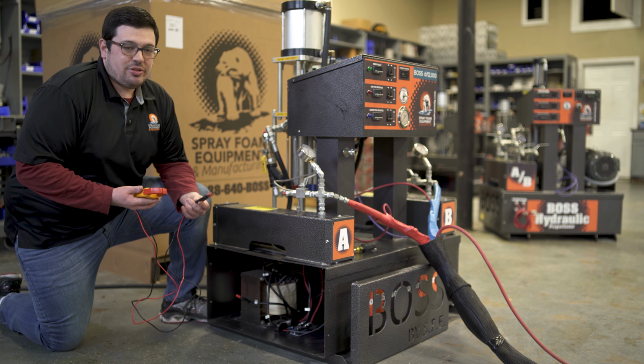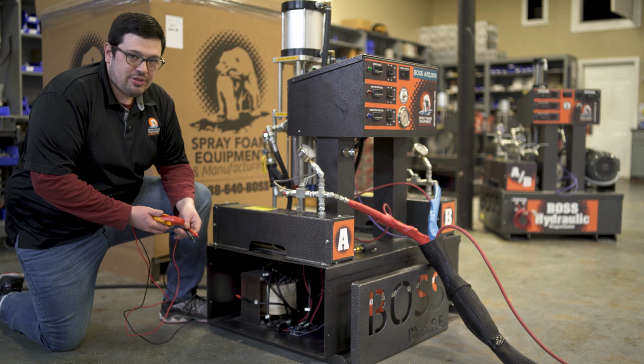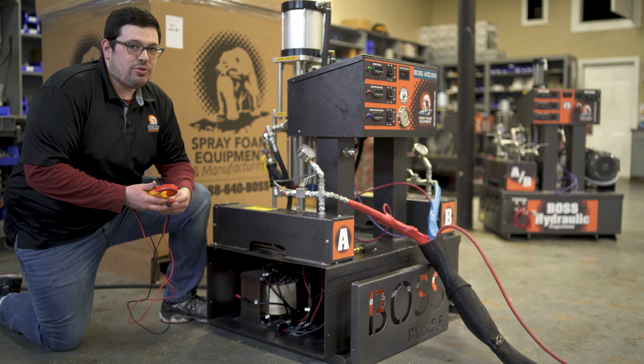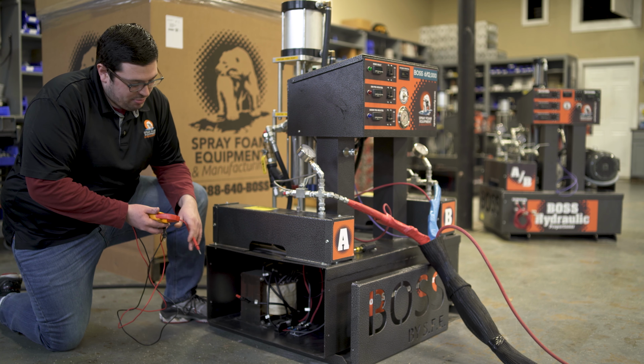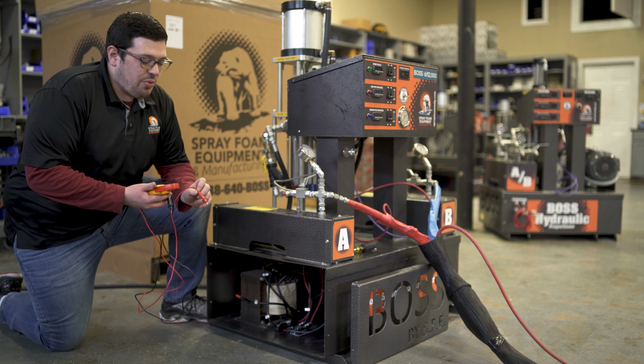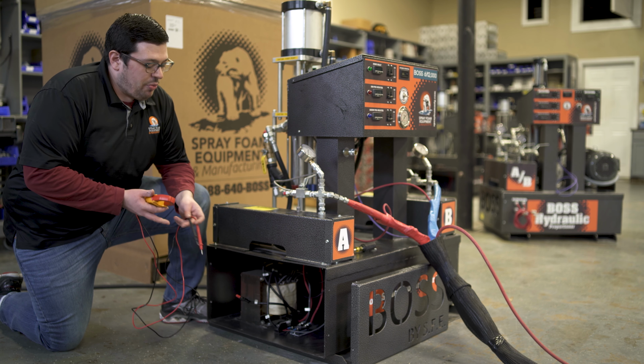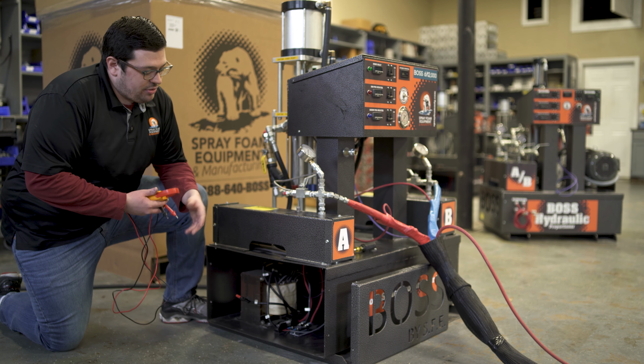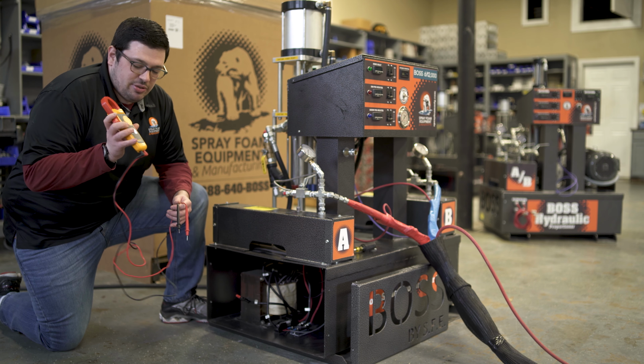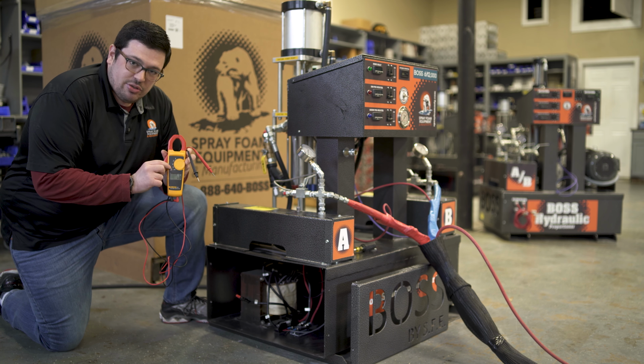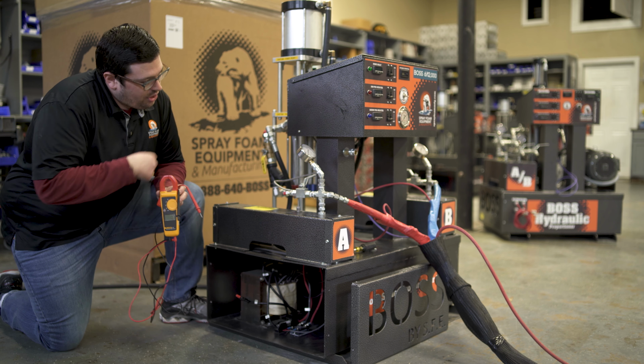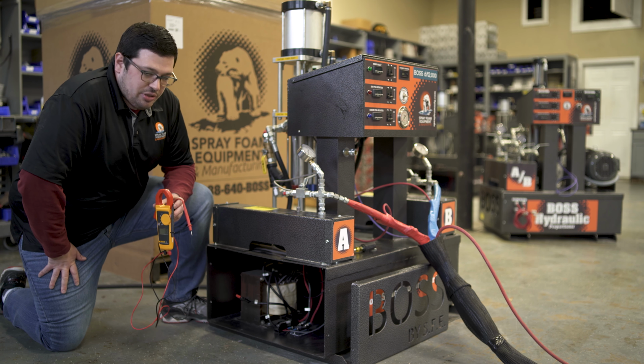So to do this test, it would be kind of hard to show you inside a machine, so we actually have a model set up that we're going to go to, and it's set up just like the inside of your machine is, but it'll be easier for me to show where you want to perform all these tests. But remember, when you're doing this test, when it comes time to actually test the voltage AC, which will be this, it'll say VAC, or have a V with a squiggly line, you want to turn on your hose heat breaker and set the controller to call for heat again.